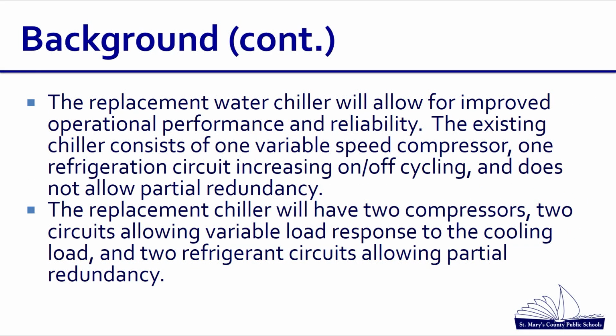The replacement water chiller will allow for improved operational performance and reliability. The existing water chiller consists of one variable speed compressor and one refrigeration circuit. This increases on and off cycling and does not allow for partial load redundancy. If something fails in one circuit, it's cooling or no cooling.